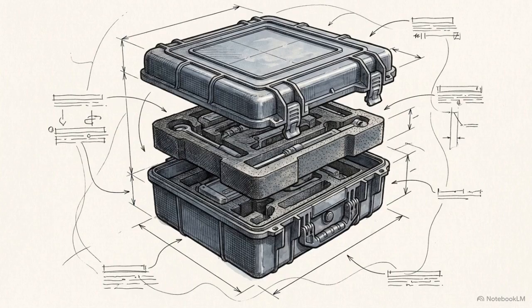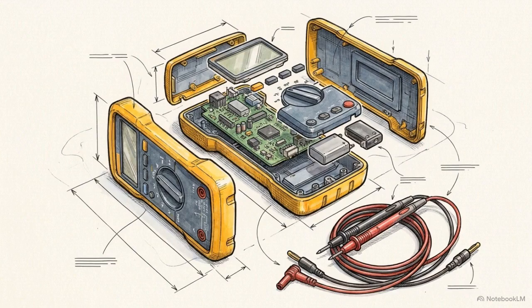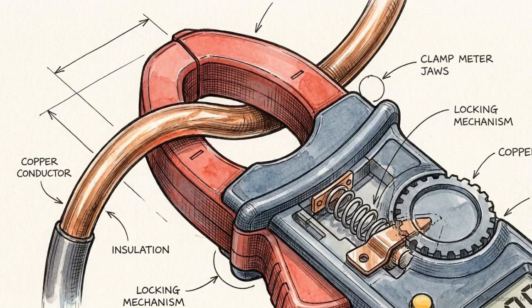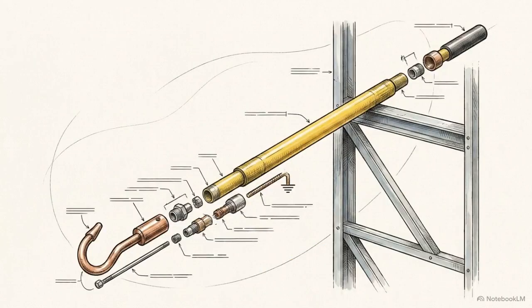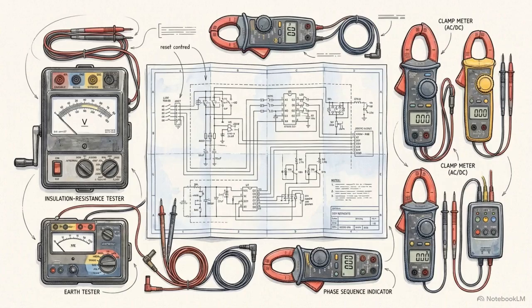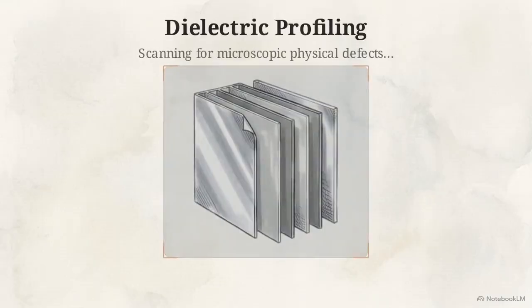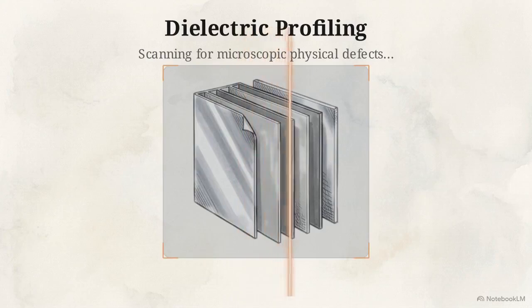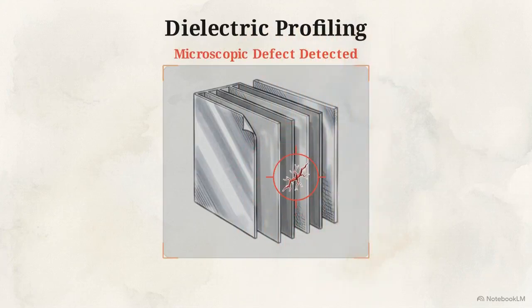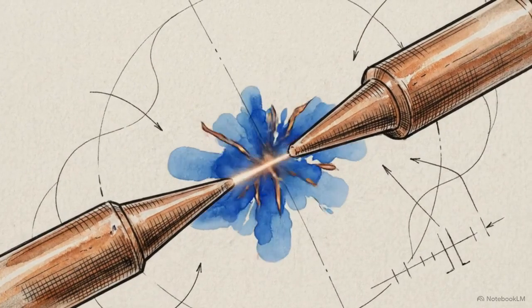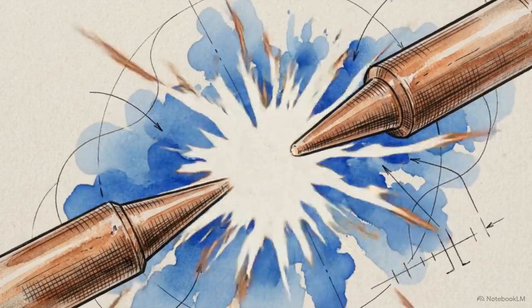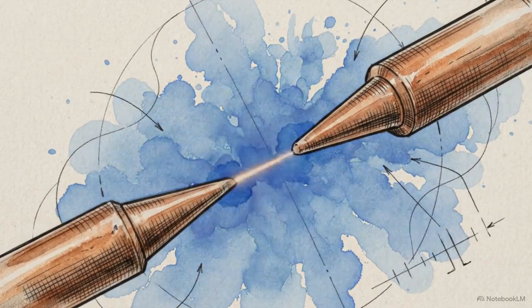Once secured, the standard loadout includes Fluke multimeters and clamp meters for basic continuity and current checks, alongside manual discharge sticks. For deeper dielectric profiling, the team uses specialized equipment, a power factor or tan-delta test instrument, and a high-voltage insulation resistance tester. These tools are specifically designed to expose microscopic physical defects. They identify early degradation in the hardware before those flaws result in a dielectric breakdown under high-voltage loads.